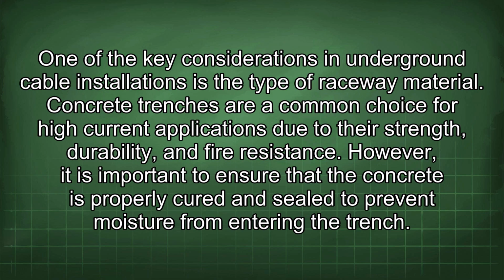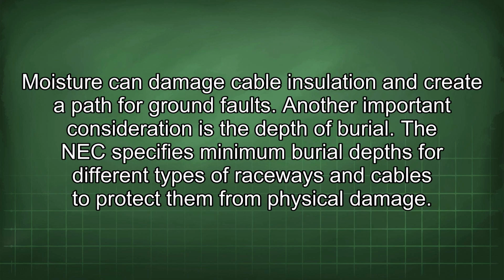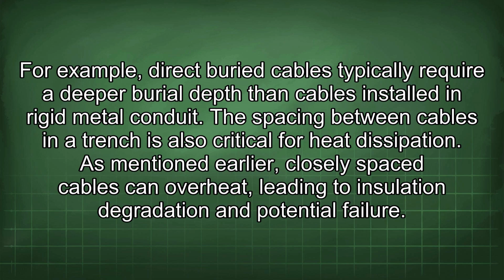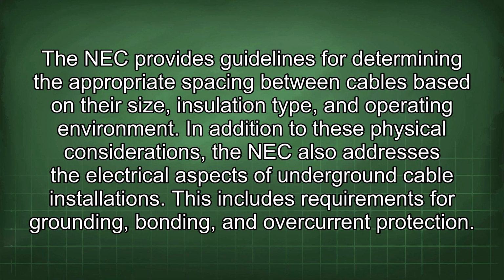One of the key considerations in underground cable installations is the type of raceway material. Concrete trenches are a common choice for high current applications due to their strength, durability, and fire resistance. However, it is important to ensure that the concrete is properly cured and sealed to prevent moisture from entering the trench. Moisture can damage cable insulation and create a path for ground faults. Another important consideration is the depth of burial. The NEC specifies minimum burial depths for different types of raceways and cables to protect them from physical damage. For example, direct buried cables typically require a deeper burial depth than cables installed in rigid metal conduit. The spacing between cables in a trench is also critical for heat dissipation. As mentioned earlier, closely spaced cables can overheat, leading to insulation degradation and potential failure. The NEC provides guidelines for determining the appropriate spacing between cables based on their size, insulation type, and operating environment.